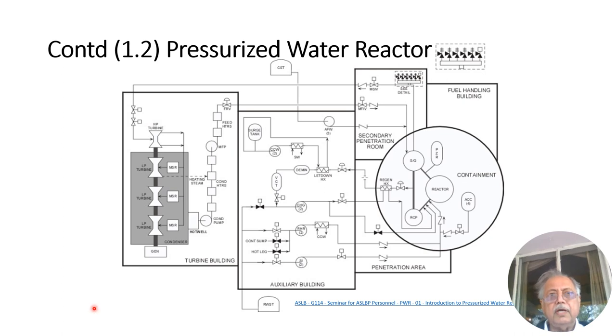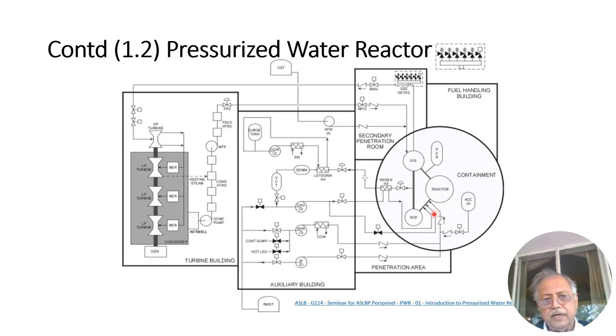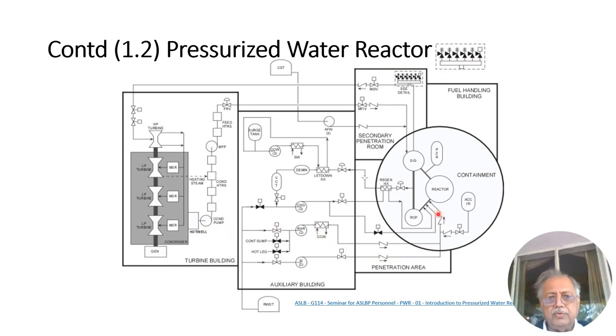Here is a better engineering layout of the pressurized water reactor. You can see the reactor, two steam generators, and the pressurizer which keeps the system at high pressure so the water doesn't boil. The cold leg takes cold water into the core; the hot leg takes hot water into the steam generators. On the secondary side, water converts into steam going into high pressure and low pressure turbines, gets condensed, and through feed pumps goes back into the reactor. The high pressure enables the inlet flow conditions to be fairly hot water.